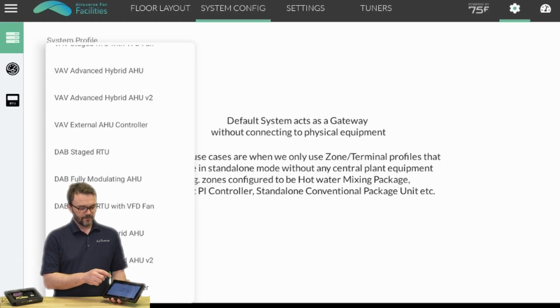If I choose DAB, dynamic airflow balancing, that's your VVT retrofit, where you're creating a weighted average of all the zones—or at least all the zone dampers—paired to this device, and then determining, based on that weighted average, how to control the AHU.